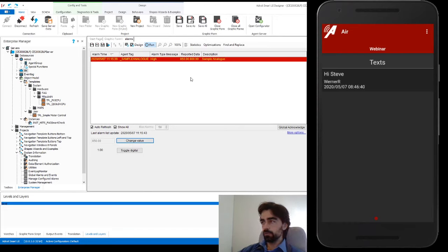So there we go, we get the alarm in the alarm viewer. This time it was quite quick with the alarm message coming through. It's on a cyclic 1 minute deadband, so depending on what time in that cycle you hit it, you'll get the message quicker than a minute, but the maximum wait time should be around a minute.